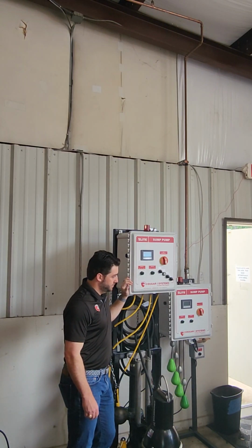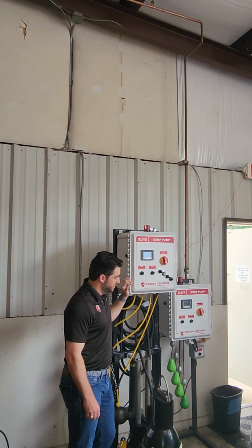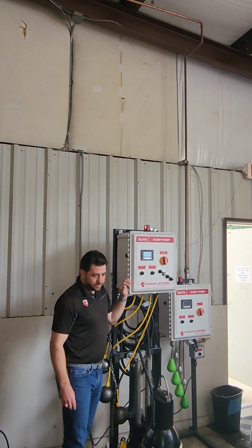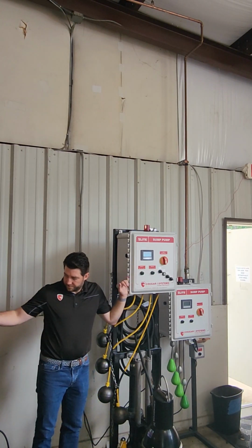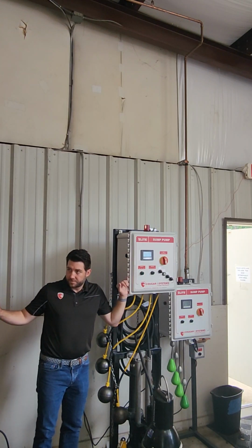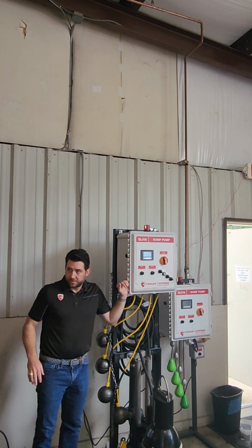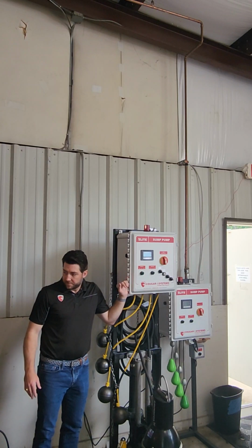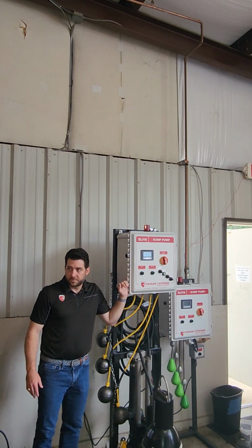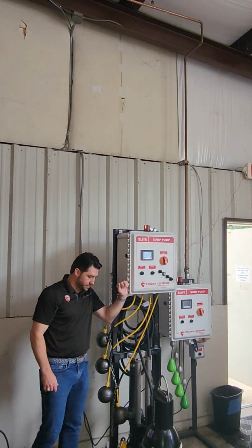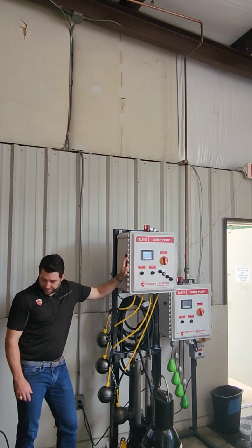You just don't want it, like I said, it all depends where the inlet's at. You don't want it backing up. So sometimes it's a little tricky. That's a good point I was about to talk about just now. You really need to consider at what point they need to be alerted that this thing's getting full. Don't put the alarm so high up that they get the alarm and their pit's already filling up and they've got backup coming inside their building. So you need to consider that when you're doing that.